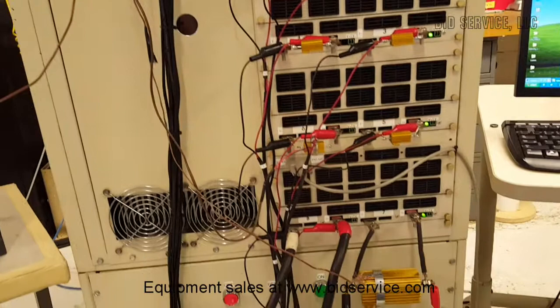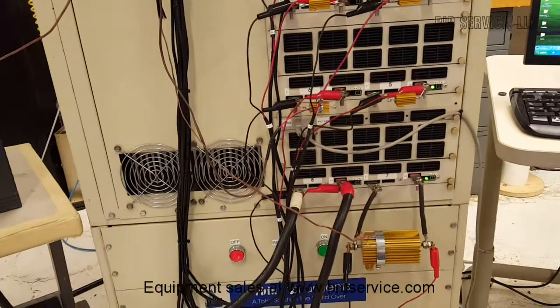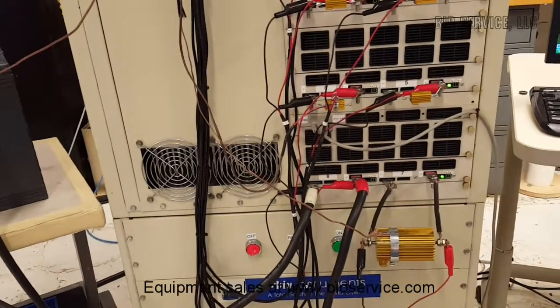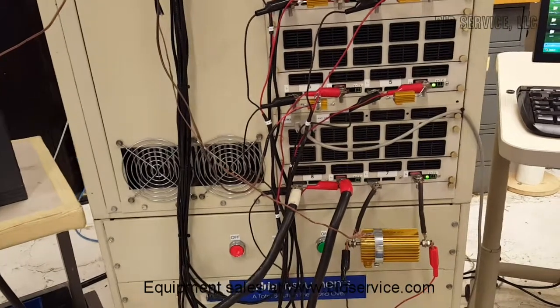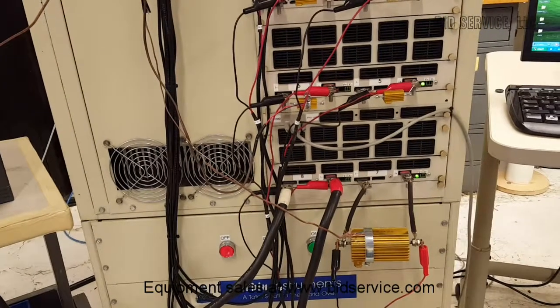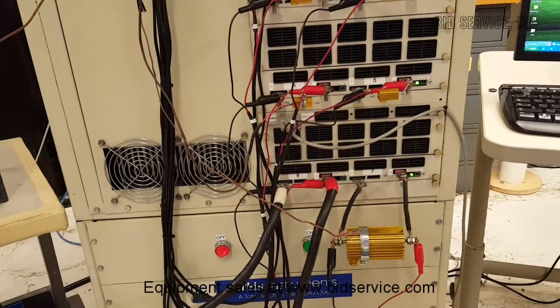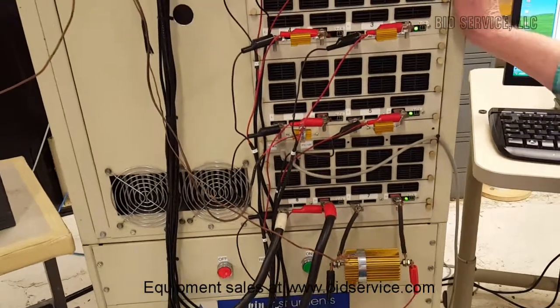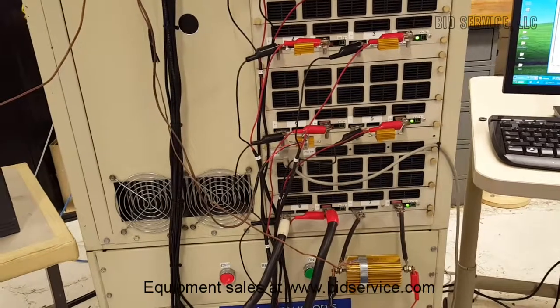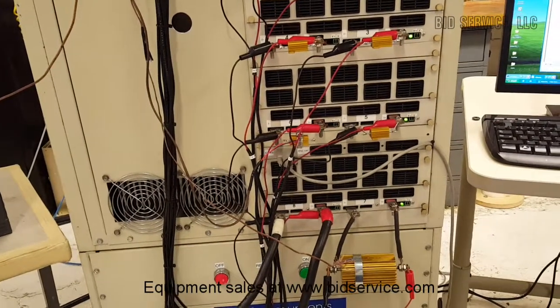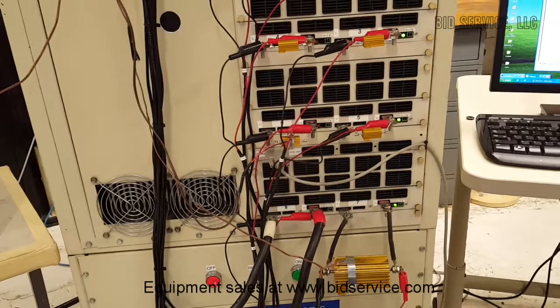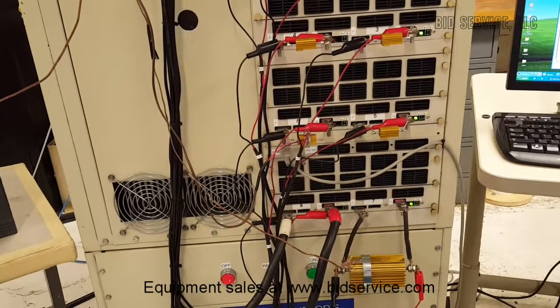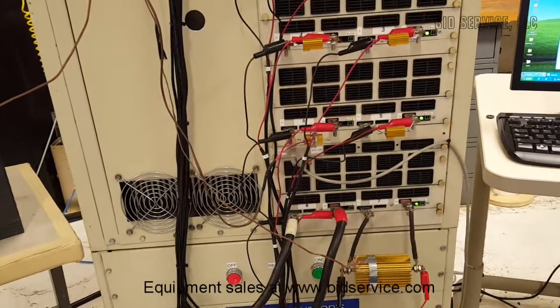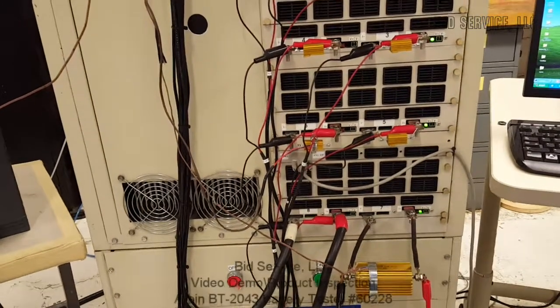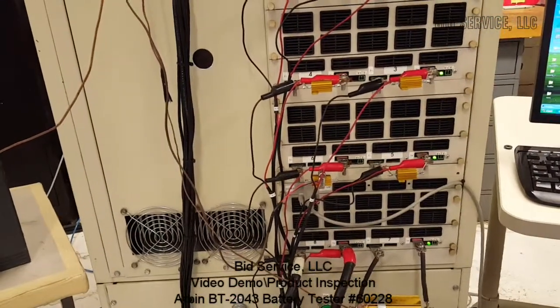So this is the entire system. Once you learn the software, it works very well. It's understandable, but it's always important to remember that you must set your safety limits. The piece of equipment has a range, but it doesn't know what you're hooking up to it. So whatever your storage or power source or battery is, make sure you know its specifications so you can set the appropriate range in the software, and you shouldn't have any problems.